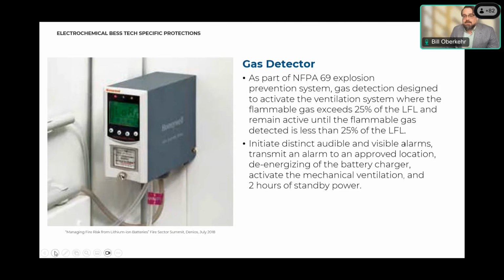A gas detection system is also going to be required specifically for that NFPA 69 explosion prevention standard to monitor the level of gas in the unit. So I keep saying below 25% of the lower flammable limit, how are you going to know that you are below 25%? You are going to use the gas detector. The NFPA 72 standard also has regulations around the signaling that comes off of the gas detector if there is an issue. So we pull in the NFPA 72 standard to make sure that the notification chain is working the way that it's supposed to be and going to the right folks. Next slide, please.